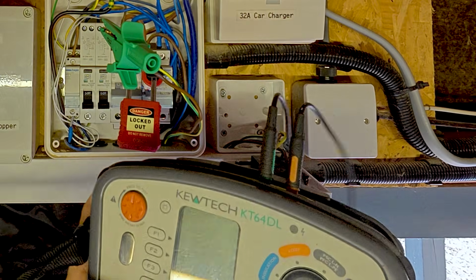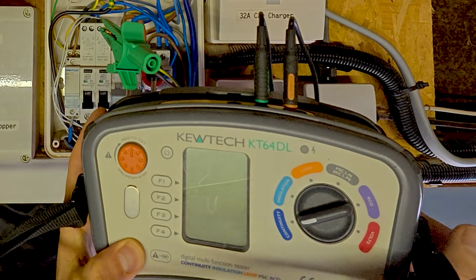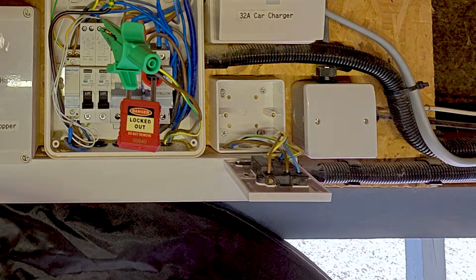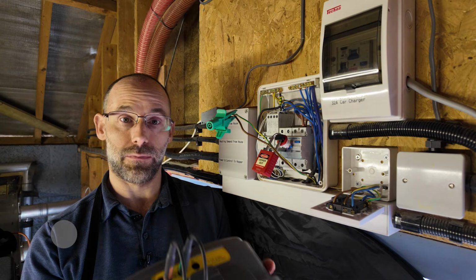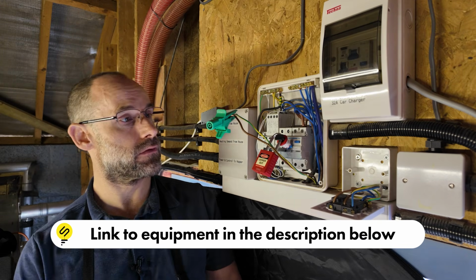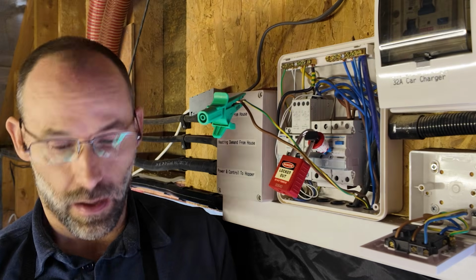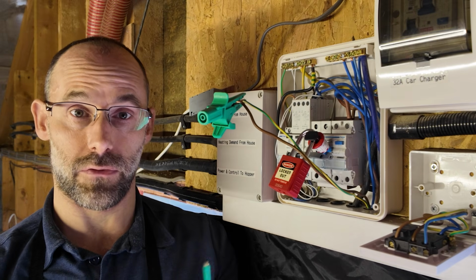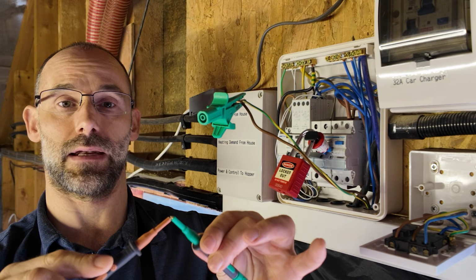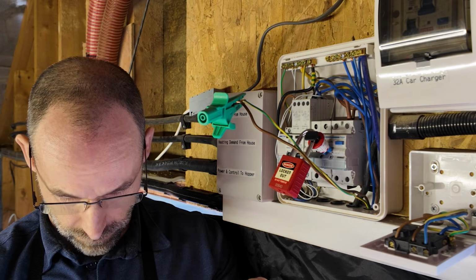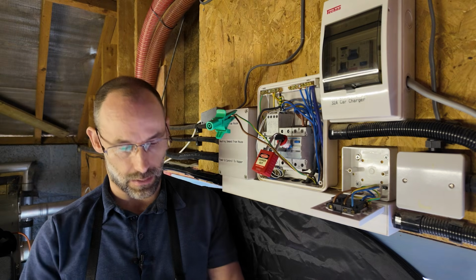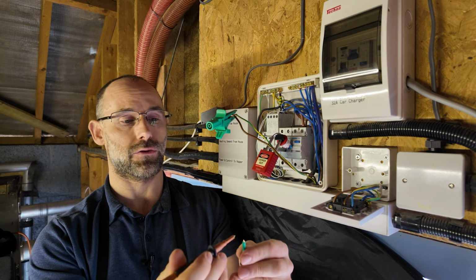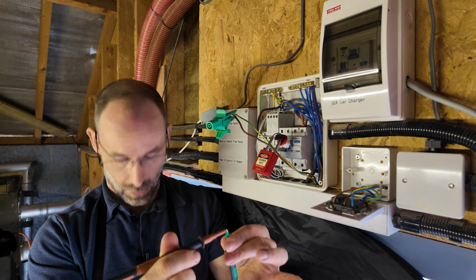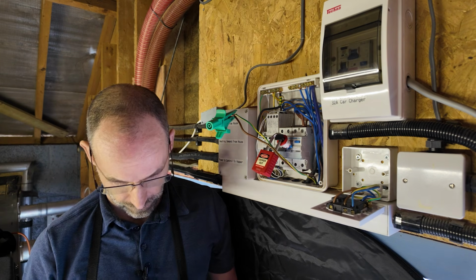So here is my multi-function tester. This is the big chunky electronics device you see electricians carry around with them. It's as big and heavy as it is for lots of reasons, which I'll go into, I think, in another video for you. So I get this on the continuity setting. This is a simple resistance meter. If my probes were connected together, then I would get a resistance reading of 0. And that's roughly what we want to see on such a short run of wires here. You may also hear a beep from the tester.